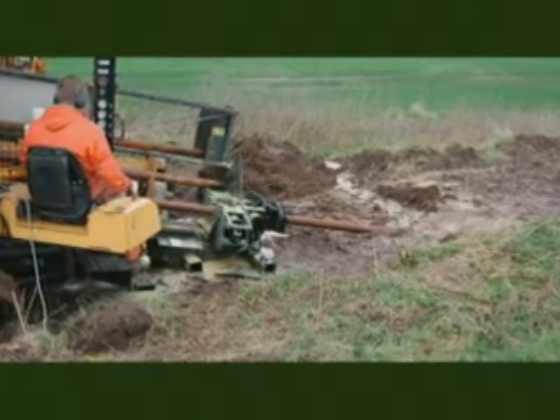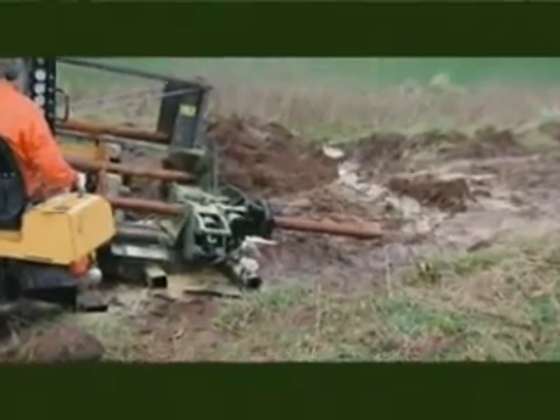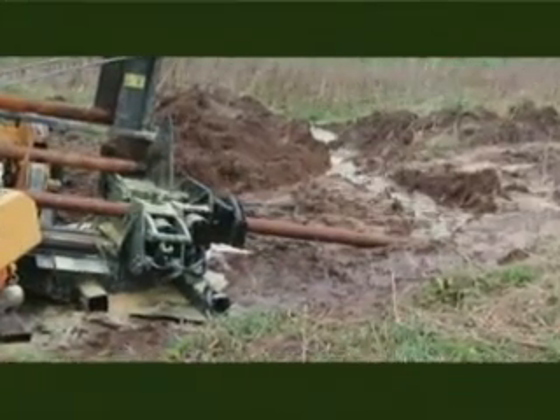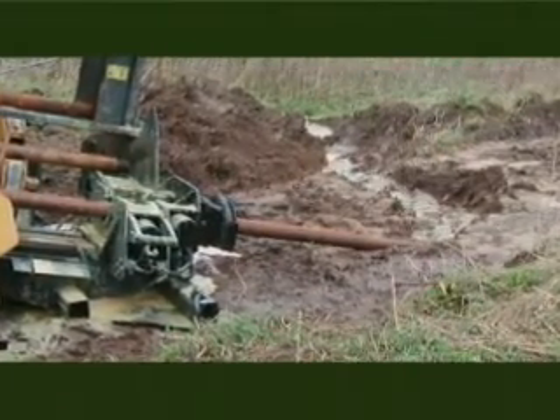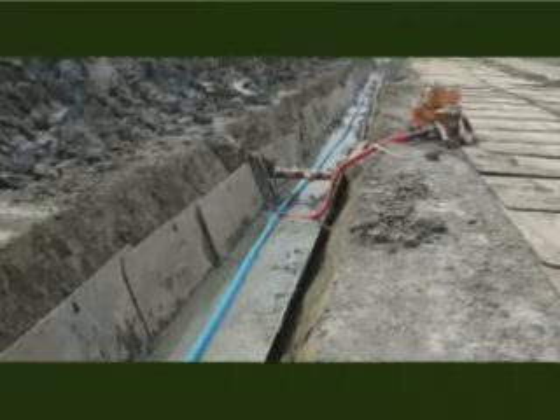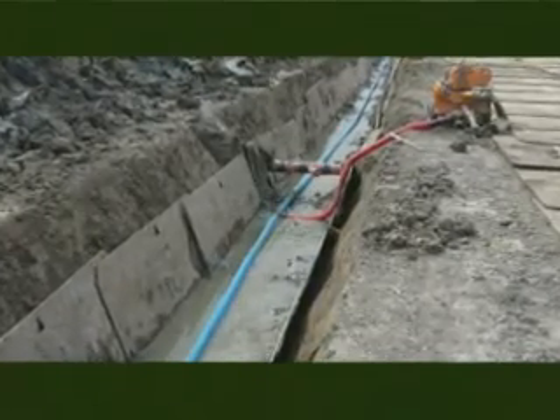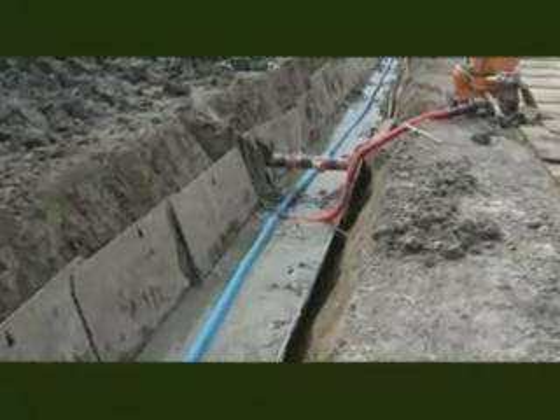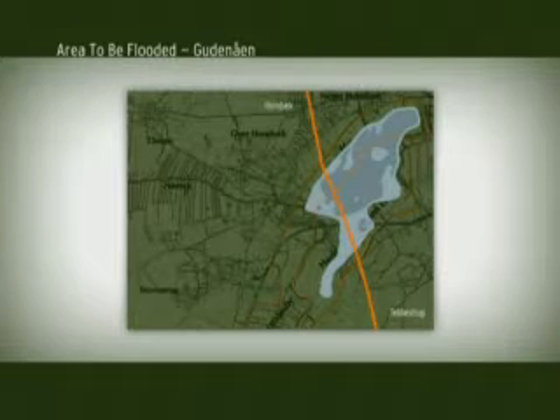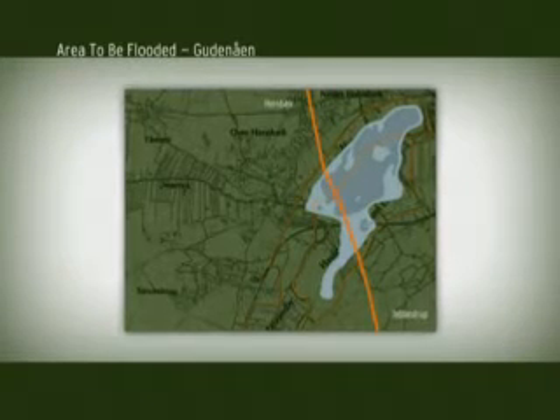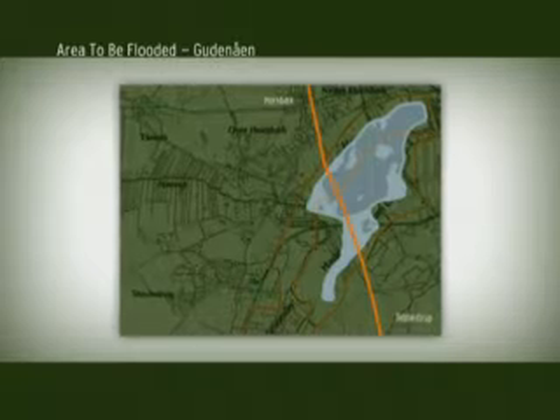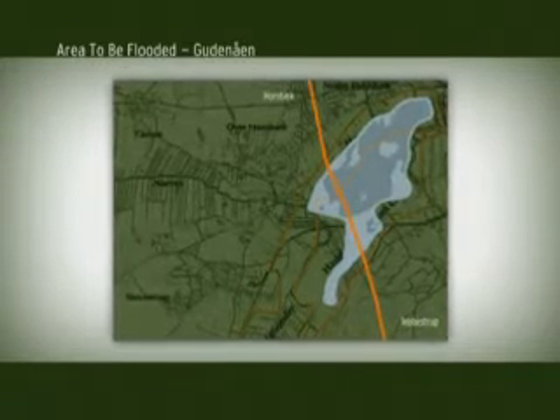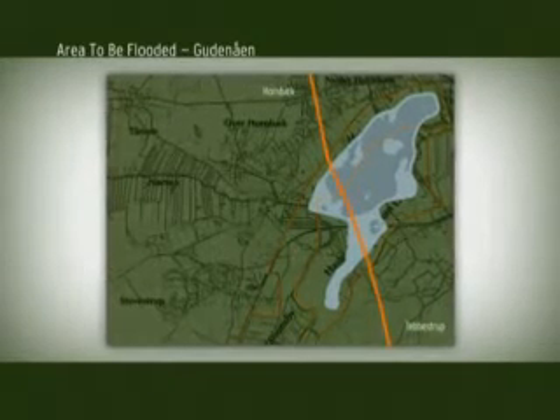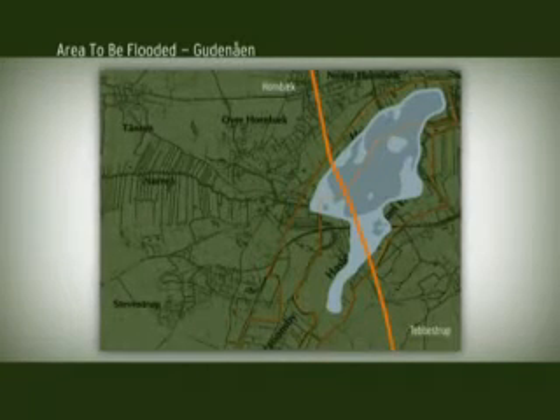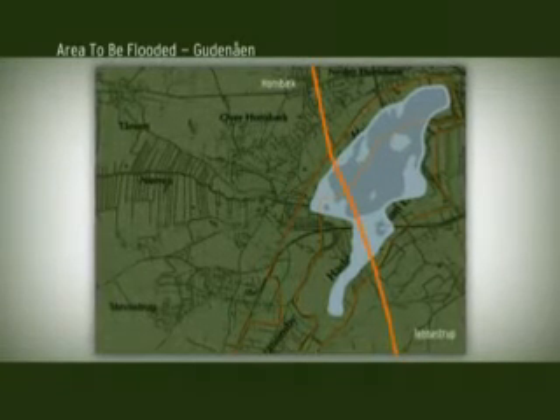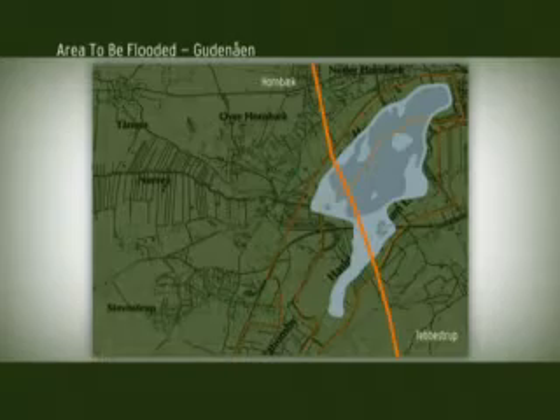It is extremely wet in Gudenåen. Prior to construction, it was necessary to dig trenches along both sides of the cable route. A drainage pipe was also laid to dewater the trench. Numerous pumps were in operation around the clock during the works. Within a few years, the authorities plan to allow the area to flood so it can return to being wet meadowlands. This means that the cables will lie in an area which is under up to 1 metre of water. The cables that were used have aluminium sheaths which protect against water.